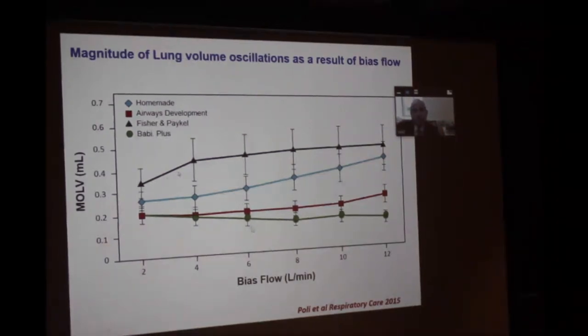The Fisher-Paykel system, shown here in black, provided the greatest magnitude of lung volume oscillation compared to any other device at all of the bias flows. The magnitude of lung volume oscillation increased at bias flow above 4 in 3 systems: the Fisher-Paykel, the homemade, and the airway development. In contrast, the Babi Plus system at flows higher than 4 showed a decrease in the oscillation.